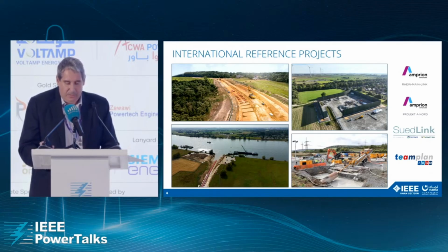The route runs in 2 parallel trenches, with each side carrying 2 high-voltage cables. The installation is mostly carried out using open construction methods at a depth of around 2 meters. To stabilize and protect the cable protection pipes, liquid soil is used, often made from locally excavated material. These construction methods ensure high operational reliability. In the event of a fault, one of the 2 lines can be repaired while the other continues to transmit electricity. These systems provide important redundancy.